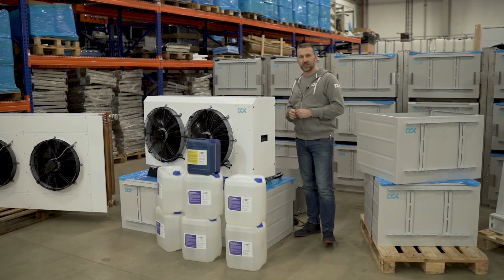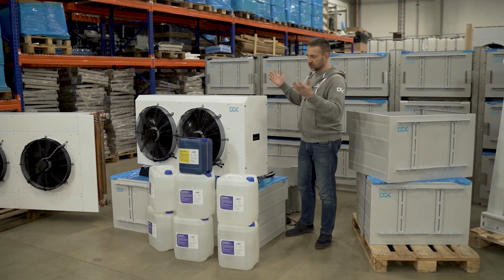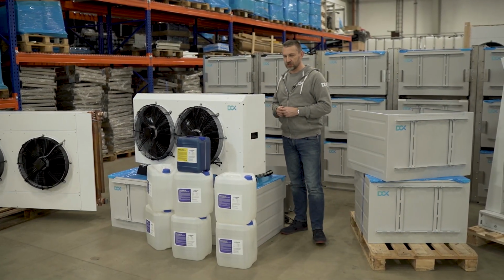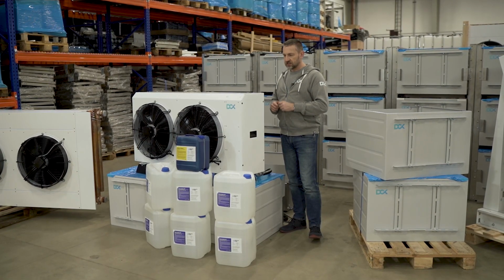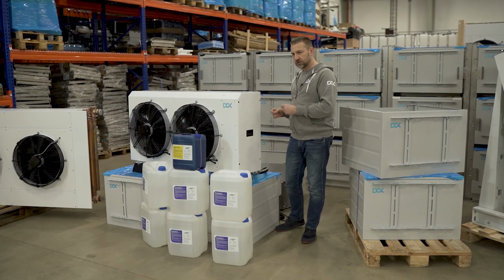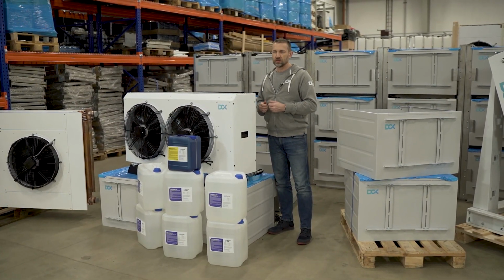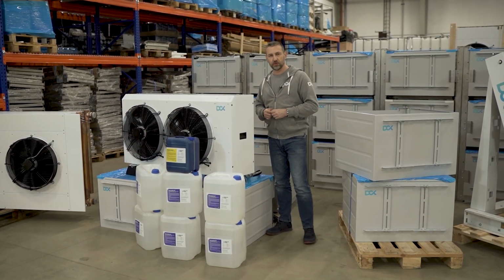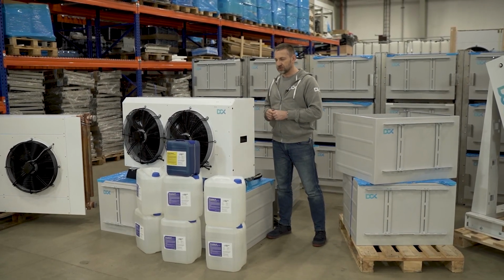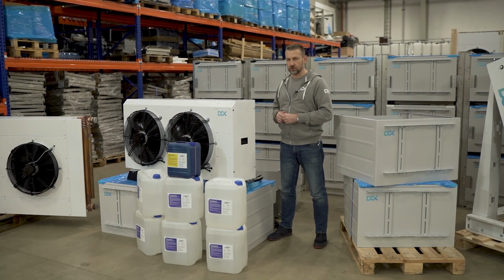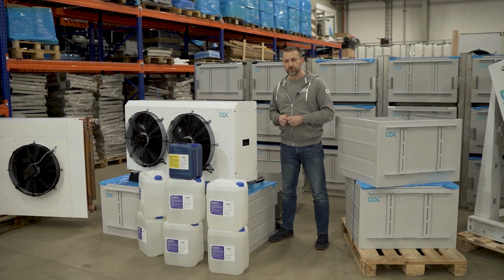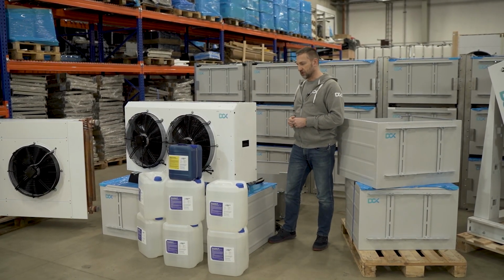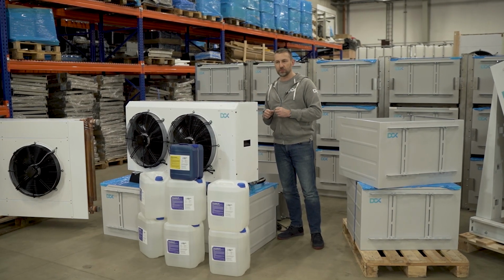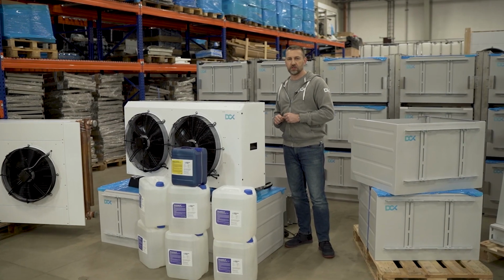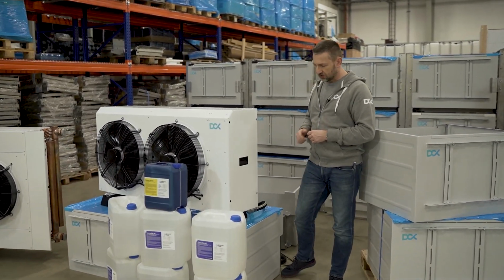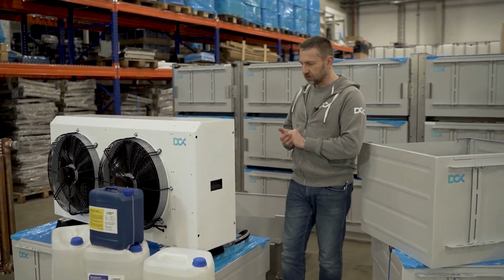But well, for the 40 kilowatt of the heat capacity, it's pretty compact compared to the systems which do not use water or water glycol mixture. So with the oil coolers, it uses water or water glycol mixture. Actually, we use demineralized water, so clean, proper water. You can call it distilled water also, depending on what will be available. And for the cold time, so winter time, you should use here water glycol mixture up to 50% of the glycol, which protects your system from freezing and being completely damaged. And it takes less, but you should be prepared to have approximately 25 liters of water here in the system, just to be on the safe side. If you lose some of the water during the filling, then you are still on the safe side.